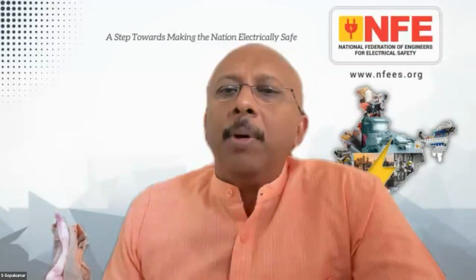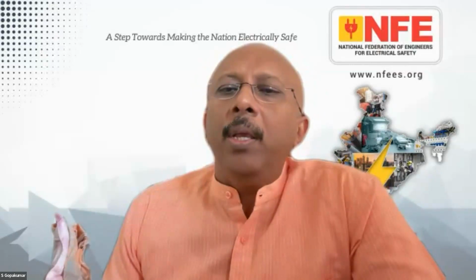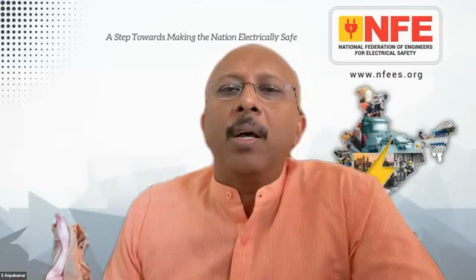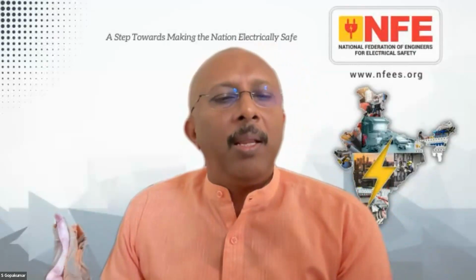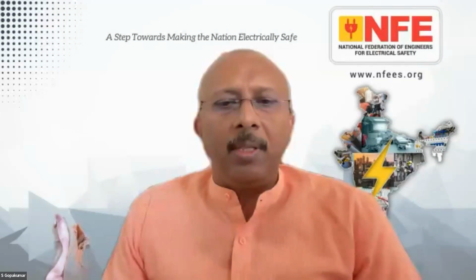Mr. Tilottaman asks, does it require double earthing with the wire, mandatory to be in an electric cabinet or enclosure? Any idea, Vishnu sir? Double earthing is what is recommended for our applications. This is just putting in redundancy, so that in case one earth wire for whatever reason is loose or gets disconnected, double earthing helps. Yes, that is the correct way.